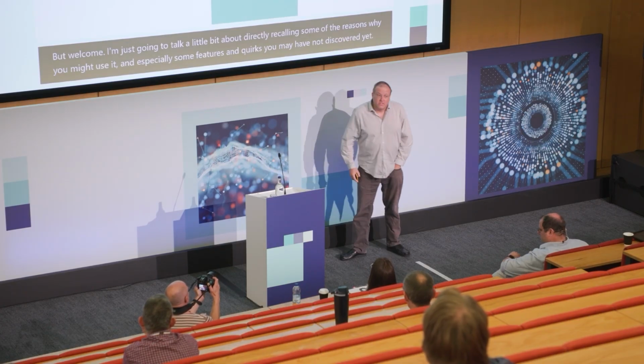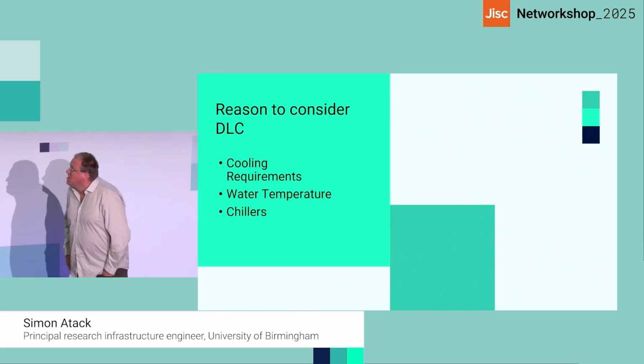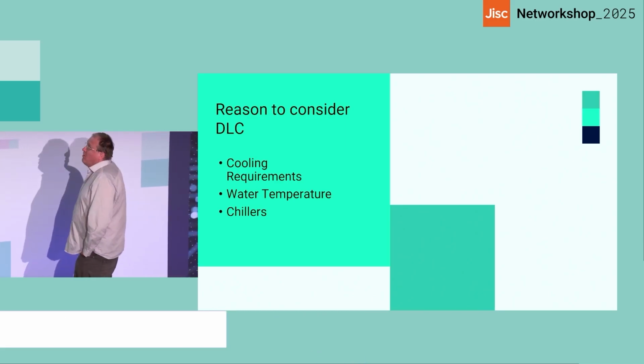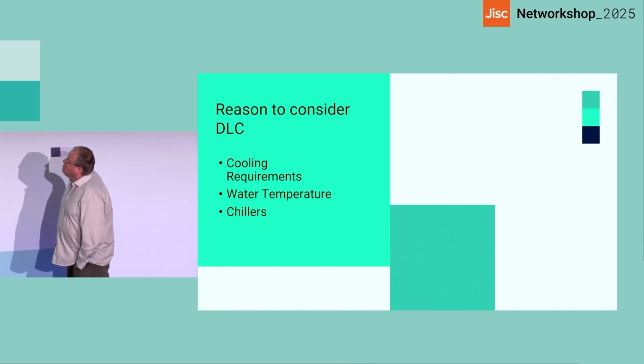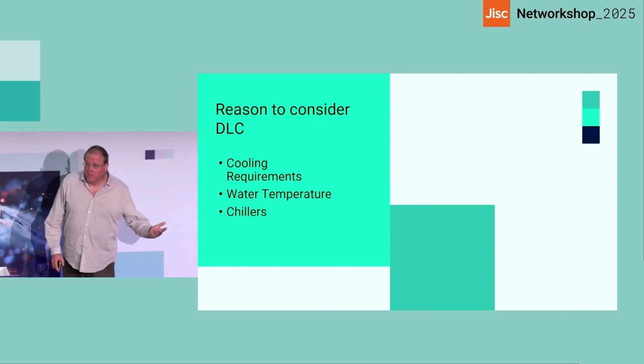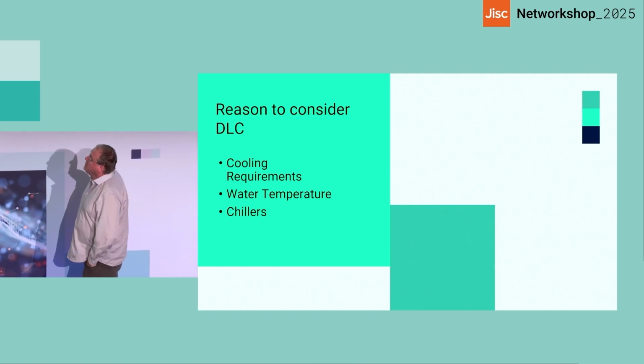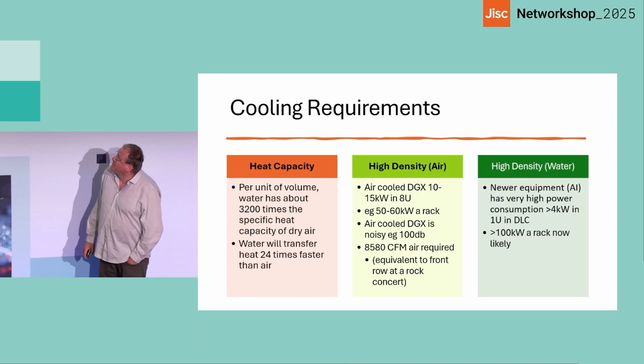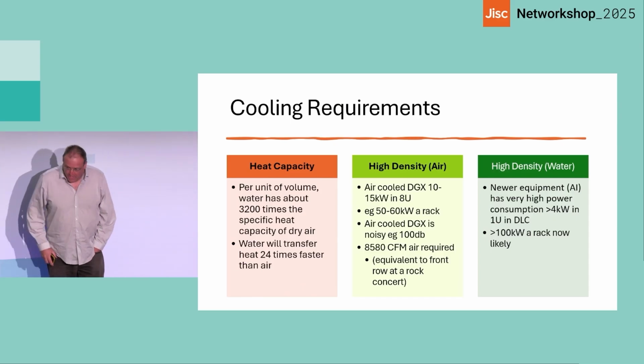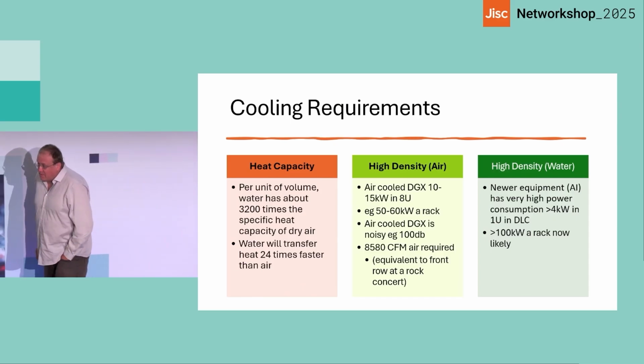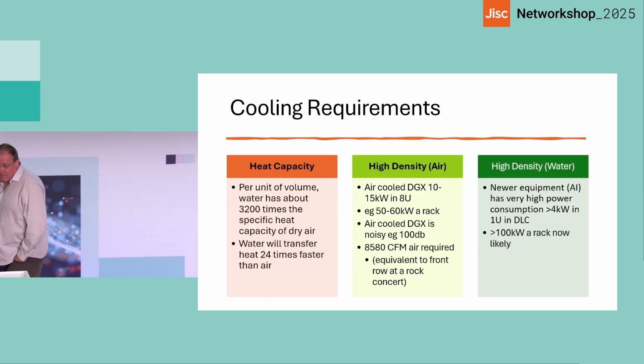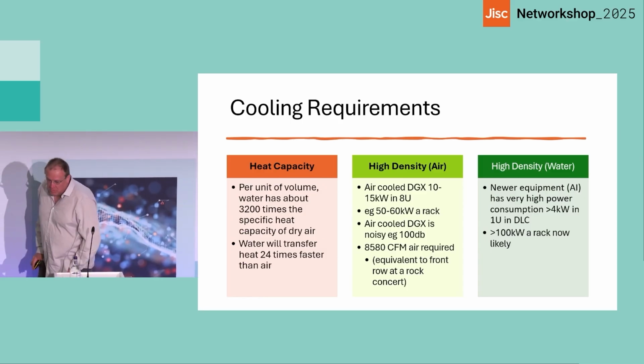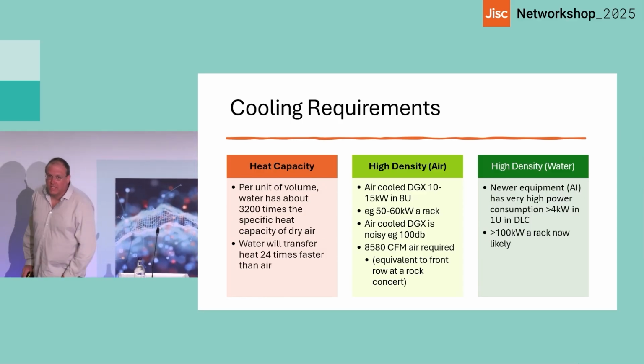So, main reasons for considering DLC, I think you'll find cooling requirements are now getting a lot more dense. Water temperatures, we can run a lot higher, so heat reuse is a lot more achievable, and a little bit about chillers. So, heat capacity. As you can see up there, heat capacity of air, it's not brilliant, it's not bad, but using water is a lot more efficient way of getting rid of the heat.